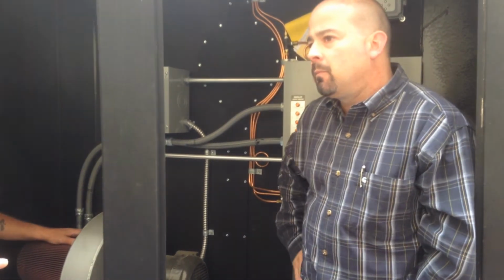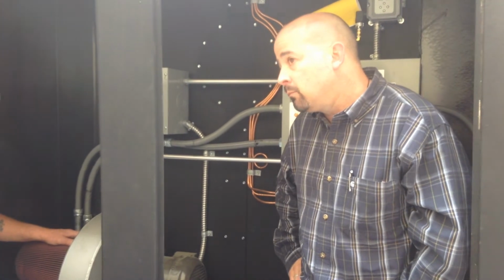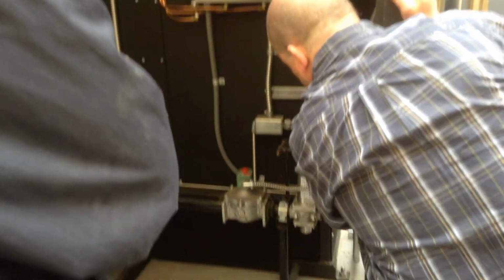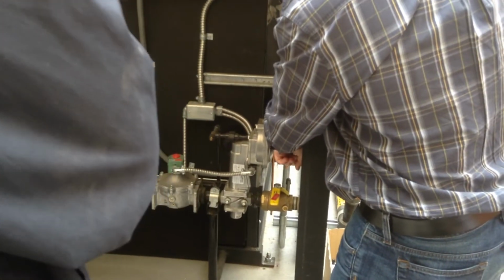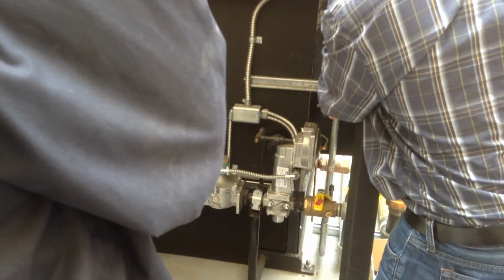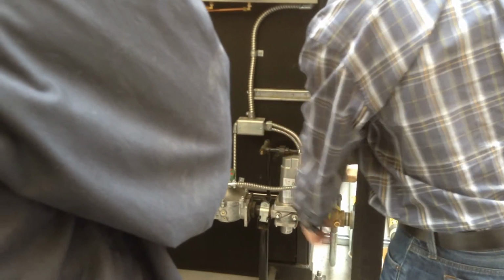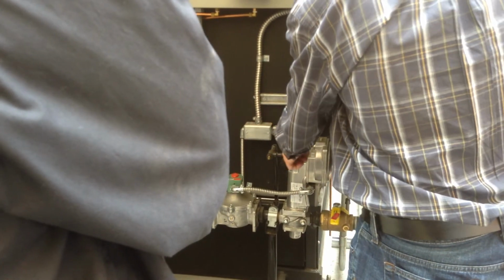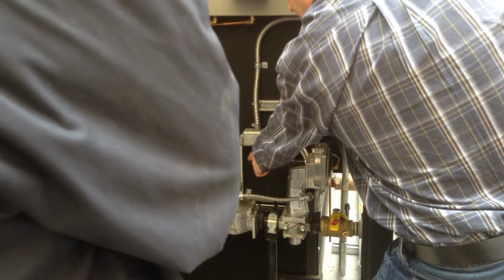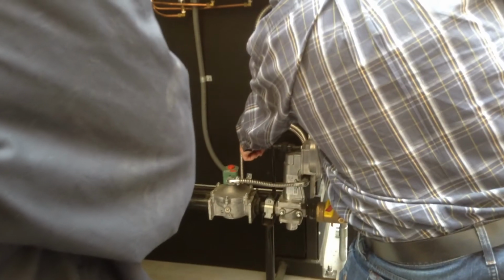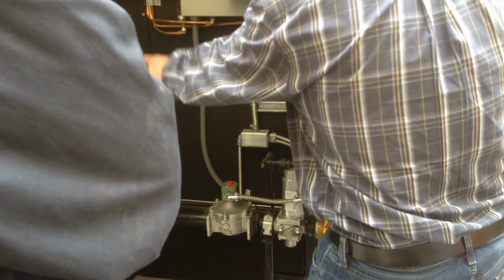Do we have a quick look at the gas line? Sure. So gas comes in on this galvanized 2-inch pipe, comes in this way. This is your manual isolation valve here. You have a 1/8 takeoff going that way. That goes to your pilot gas train. So your pilot gas train consists of a strainer, that brass strainer, a regulator, and then a 120 volt solenoid gas valve. That's your pilot train.